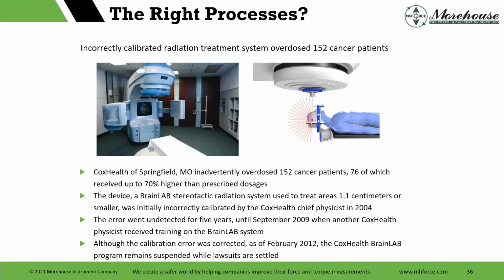The device, a BrainLab stereotactic radiation system used to treat areas 1.1 centimeters or smaller, was initially incorrectly calibrated by a Cox Health chief physicist in 2004. The error went undetected for 5 years until September 2009, when another physicist received training on the system. Someone actually received training, followed the training, said, oh crap. They admitted it, although the calibration error was corrected as of February 2012. The program still remains suspended, and I have not looked recently. It was still suspended for a long time after that, and there's a large trove of information, and no patients were observed to have symptoms of increased radiation exposure. There was no prompt for them to ever investigate.